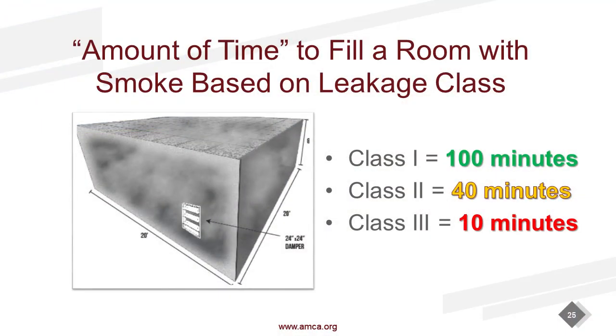for the occupant. So let's say this room is 20 feet by 20 feet with an 8-foot ceiling. I've got a 24 by 24 smoke damper, ducted. Let's pretend it's closed. Let's pretend there's smoke circulating through that ductwork. If that damper was Class 3 rated, that room would fill up with smoke in 10 minutes. That is not a very effective damper. That's why we don't use them in the U.S.